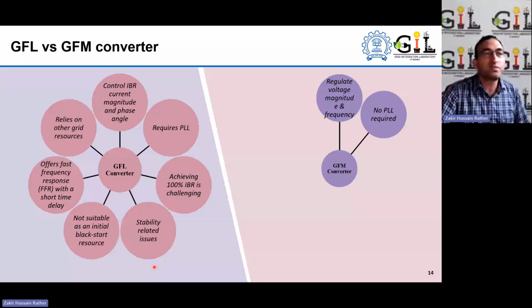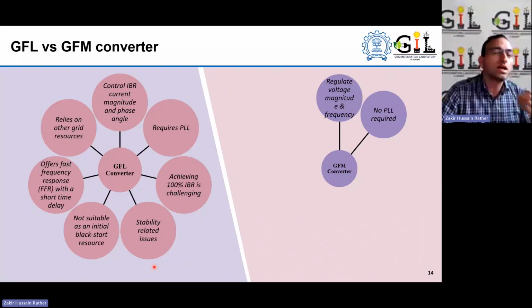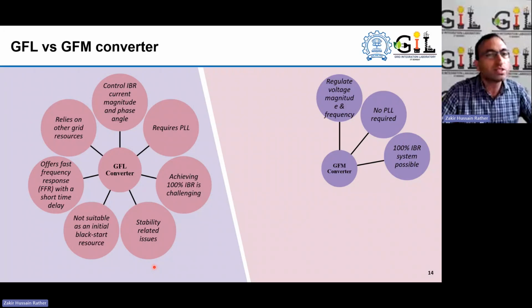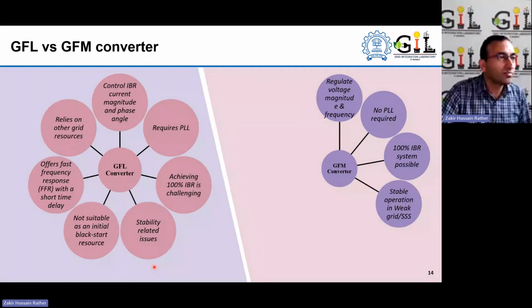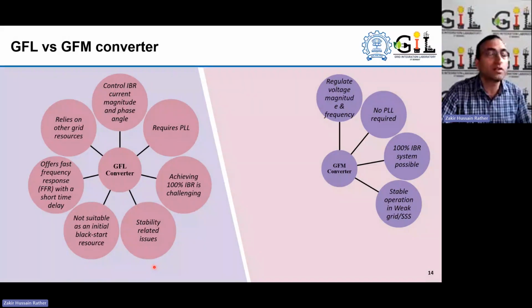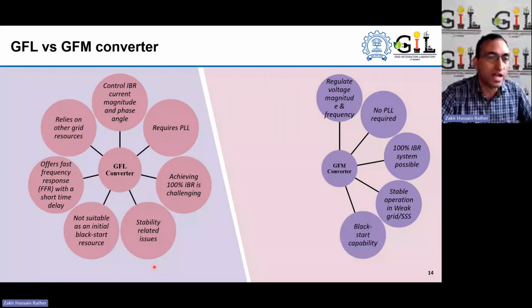It does not need the PLL because, as I mentioned earlier, it is behaving similar to conventional generators. So the moment it is synchronized, it remains synchronized with the grid. A 100% IBR system is, technically speaking, possible with grid forming technology. Particularly in weak grids, grid following technology has a lot of challenges, and grid forming actually has that capability to operate in weak grids, and then it improves the system strength of the grid as well.